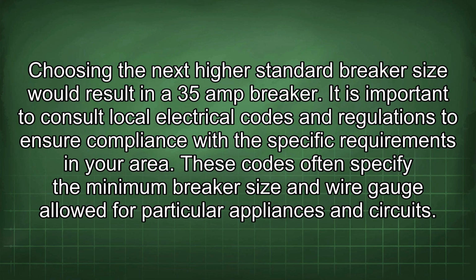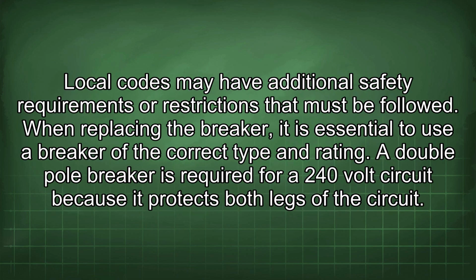It is important to consult local electrical codes and regulations to ensure compliance with the specific requirements in your area. These codes often specify the minimum breaker size and wire gauge allowed for particular appliances and circuits. Local codes may have additional safety requirements or restrictions that must be followed. When replacing the breaker, it is essential to use a breaker of the correct type and rating. A double pole breaker is required for a 240 volt circuit because it protects both legs of the circuit.